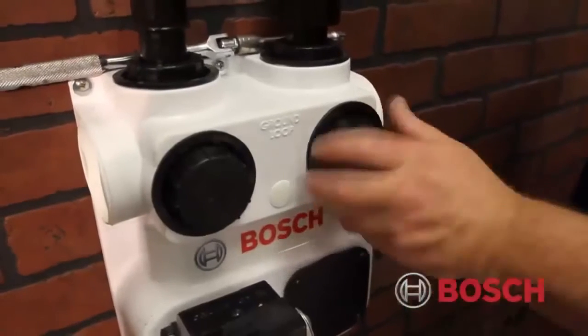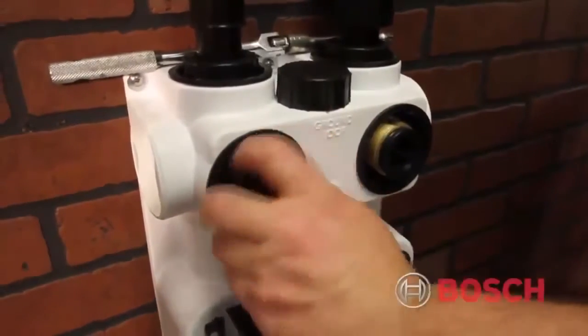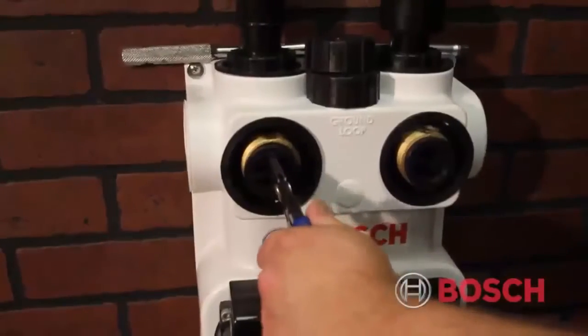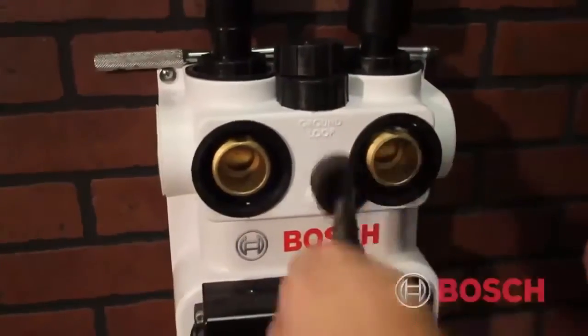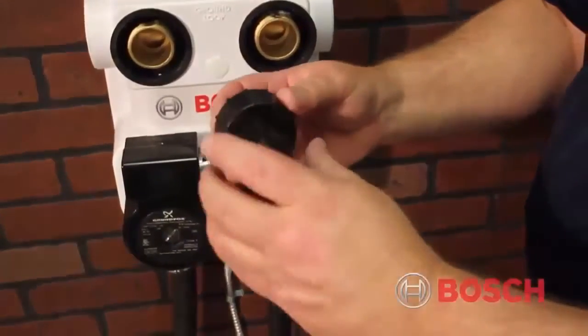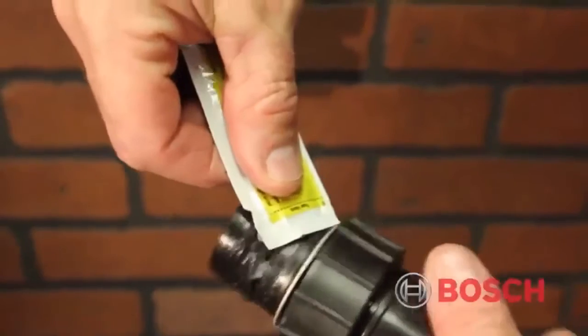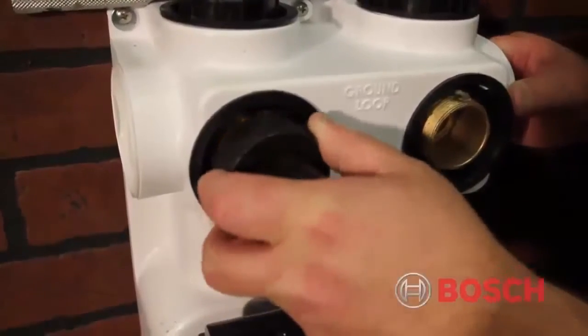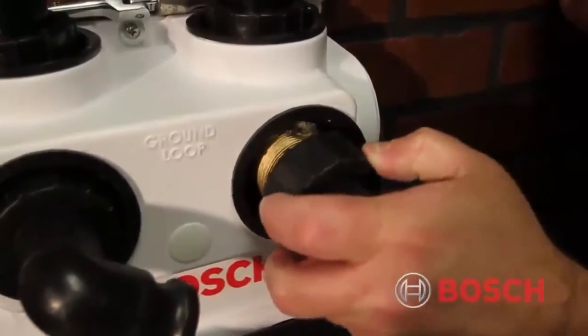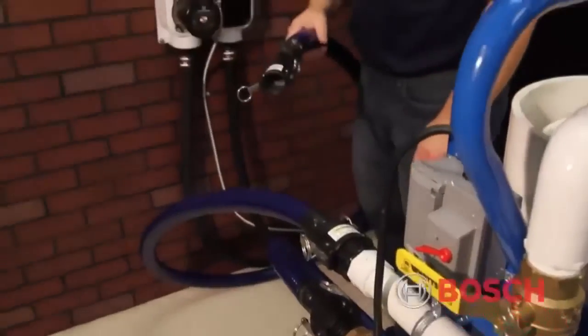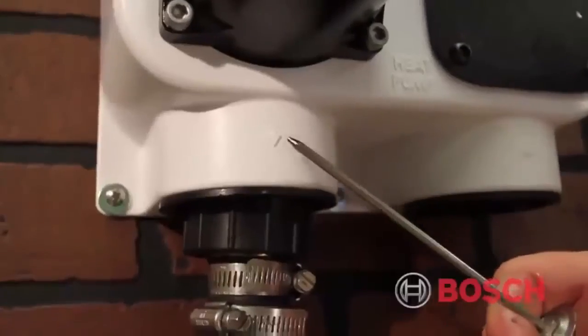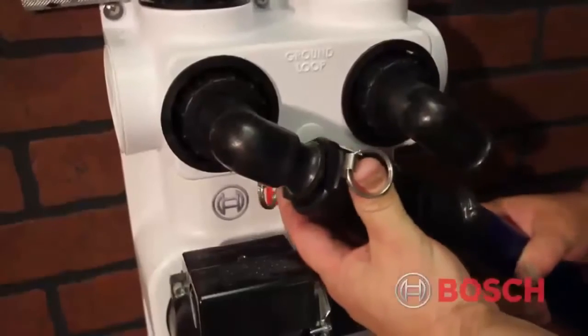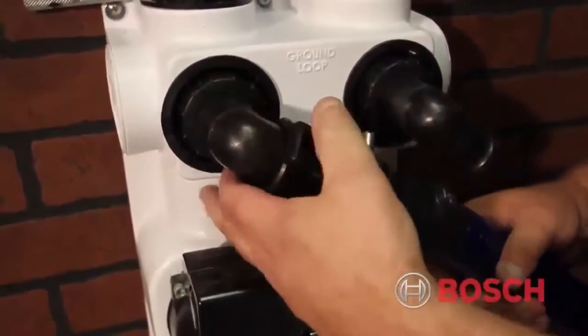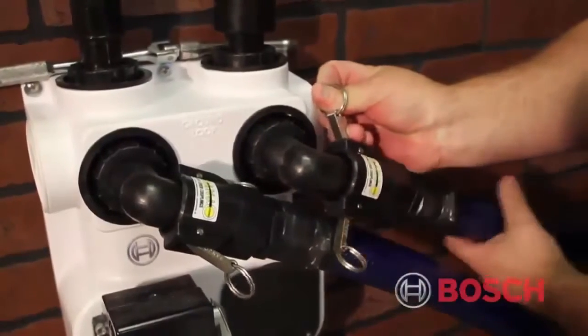The first step is to remove the flow center flush port caps and then remove the double O-ring flush port plugs. Next, install the 1.5-inch double O-ring flush cart connectors. Be sure to lubricate O-rings prior to install. Next, attach the return hose connection of the flush cart to the water inside of the flow center, and then make your discharge hose connection to the water outside of the flow center.